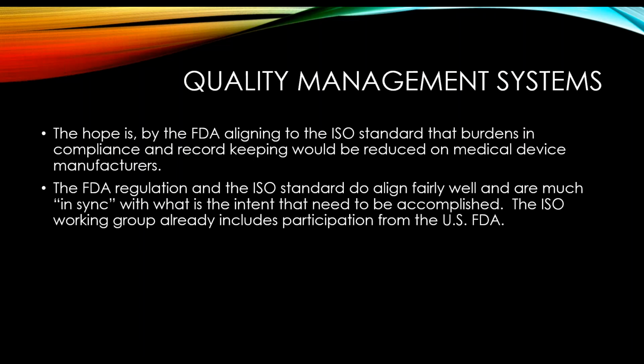One of the things I wanted to do probably for the last 5 to 10 years is my program, I would love to have ISO 13485. Well, for the program that I'm in right now, that would probably cost several $100,000 at least to accomplish. Because I have 28 acute care hospitals, I have freestanding EDs, I have surgery centers, I have imaging centers. I have all of those under my responsibility where we service and maintain equipment. When you go for an ISO accreditation, you have to have them surveyed. So the cost to go out and have an accredited body, a notified body, survey those sites, those costs are all borne by the folks going after that accreditation.